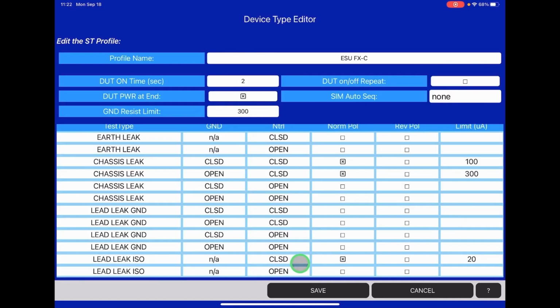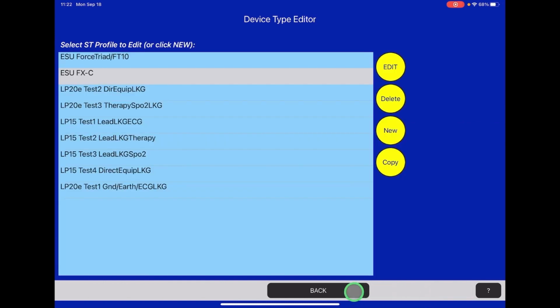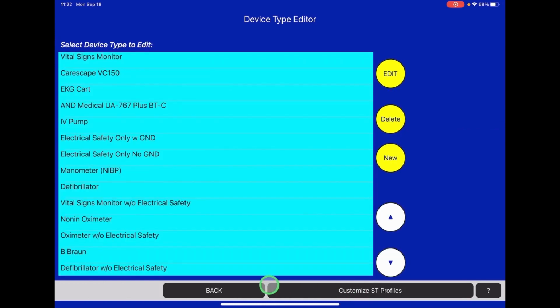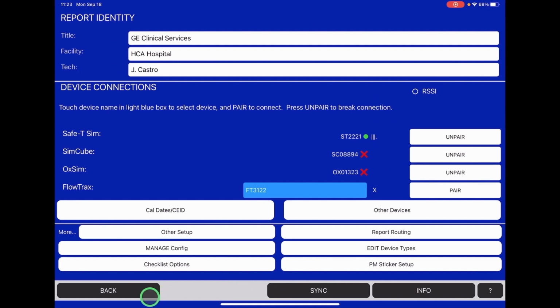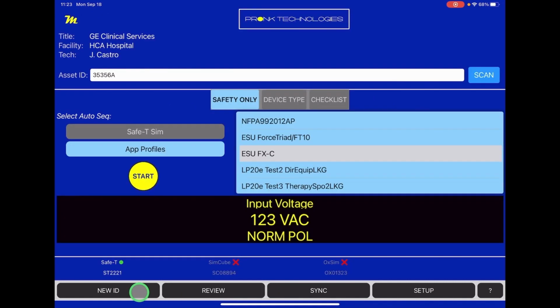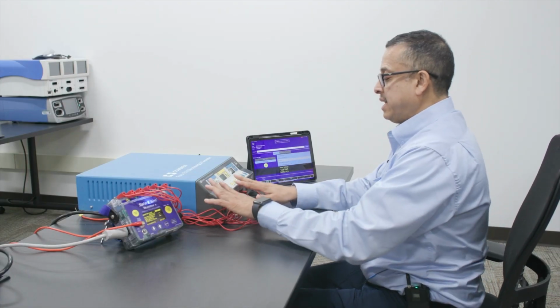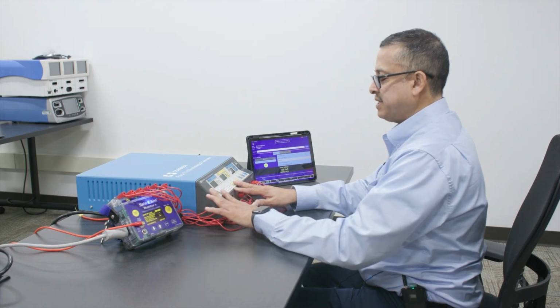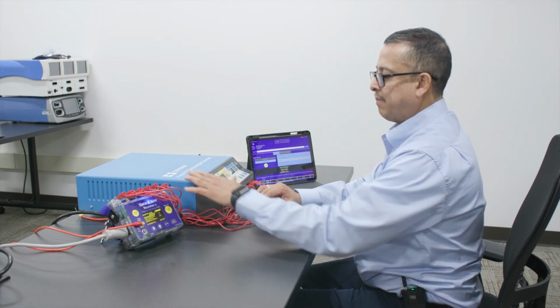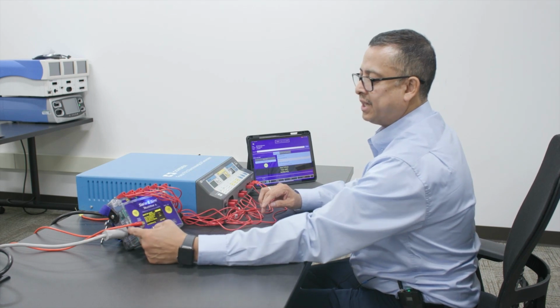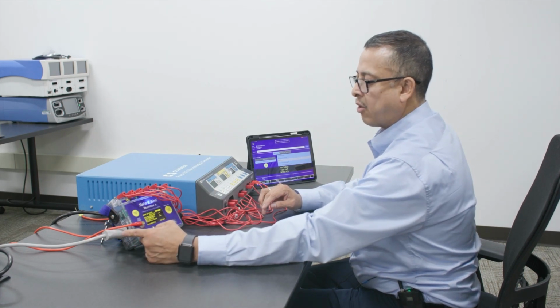So we need to make sure we've configured the test. We went ahead and done that, and we can be ready to perform this test. So we have the device, the app set up ready to do this test. It will communicate to the safety analyzer to perform it once we're ready. Now we need to get the actual ESU connected to the safety sim. To do that, we of course want to plug it in to the unit, the safety analyzer here on the left, plug in the power cord to it.